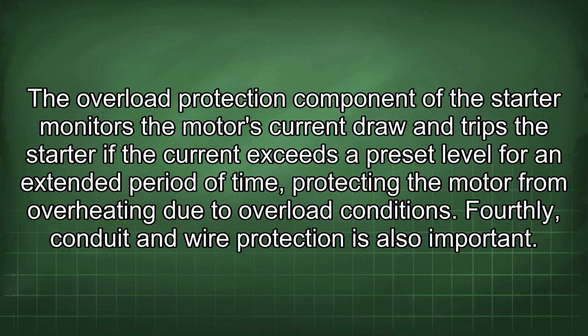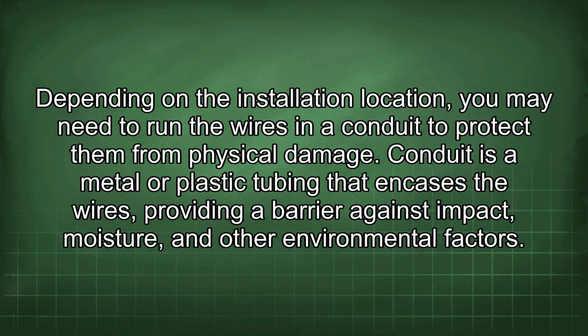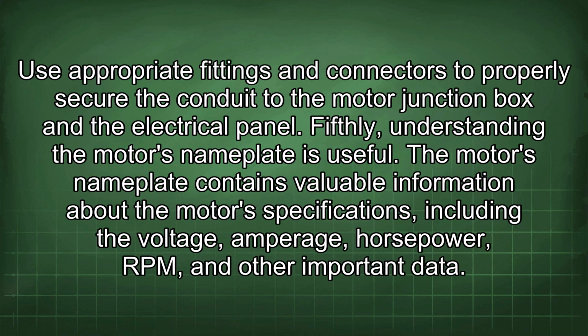Fourthly, conduit and wire protection is also important. Depending on the installation location, you may need to run the wires in a conduit to protect them from physical damage. Conduit is a metal or plastic tubing that encases the wires, providing a barrier against impact, moisture, and other environmental factors. Use appropriate fittings and connectors to properly secure the conduit to the motor junction box and the electrical panel. Fifthly, understanding the motor's nameplate is useful.